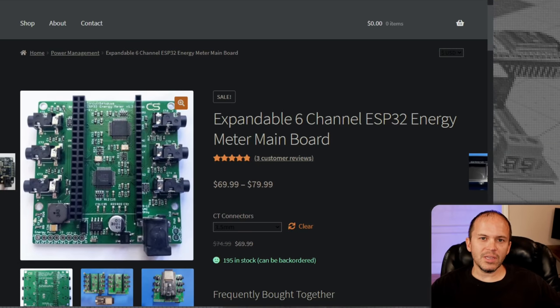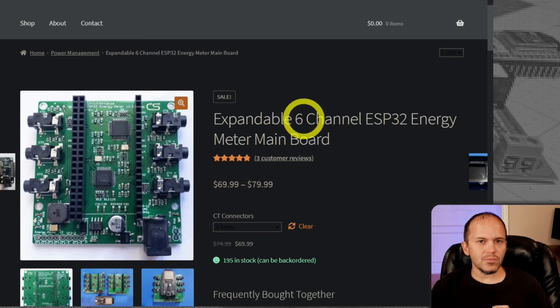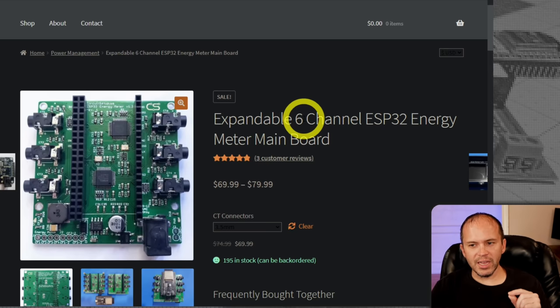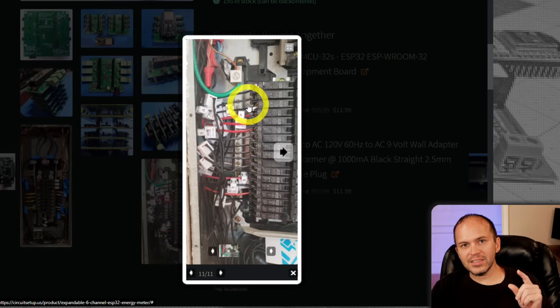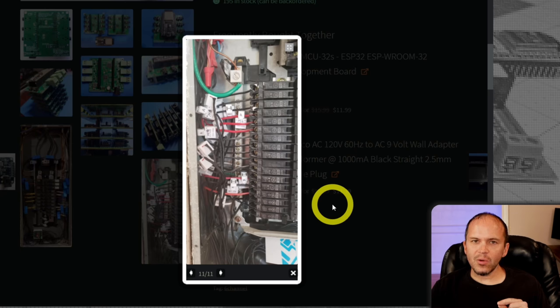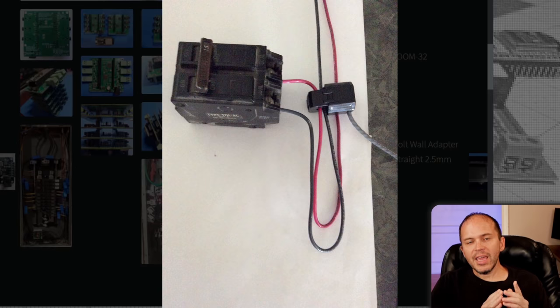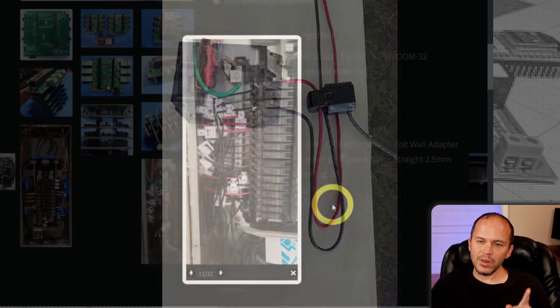I highly recommend testing this on the bench first — use a little wire, get it all configured so you're not wasting time during installation. For the CT clamp, you don't want to go over two wires because if they're out of phase they'll cancel each other out — just put it on one hot wire. If you have room on your air conditioning or dryer, you can have one lead go through the clamp one direction and the other lead come back through the other direction, and it will add those up for you.